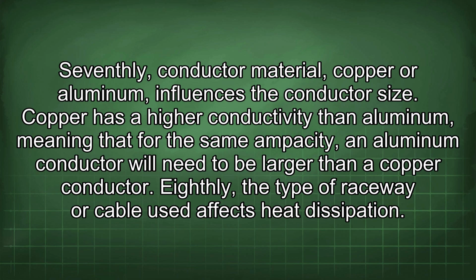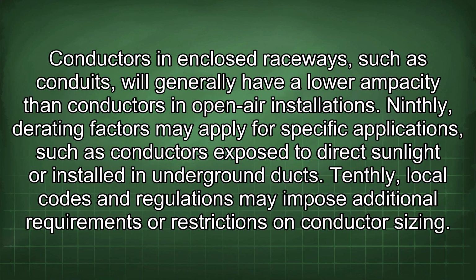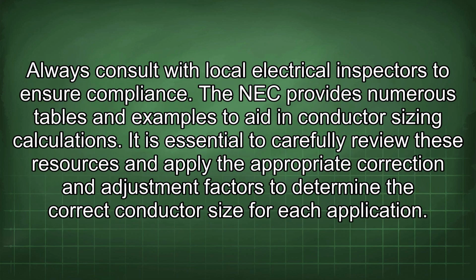Eighthly, the type of raceway or cable used affects heat dissipation. Conductors in enclosed raceways, such as conduits, will generally have a lower ampacity than conductors in open-air installations. Ninthly, derating factors may apply for specific applications, such as conductors exposed to direct sunlight or installed in underground duct. Tenthly, local codes and regulations may impose additional requirements or restrictions on conductor sizing. Always consult with local electrical inspectors to ensure compliance.